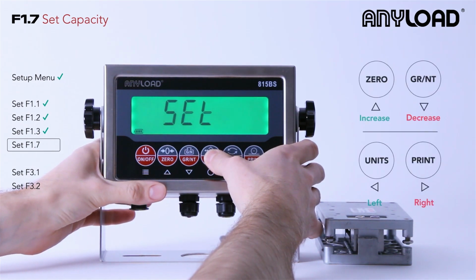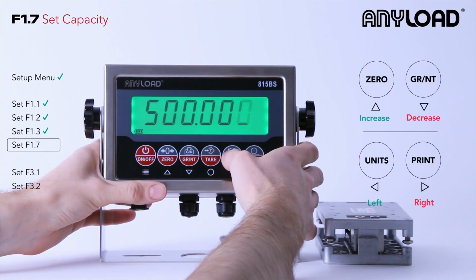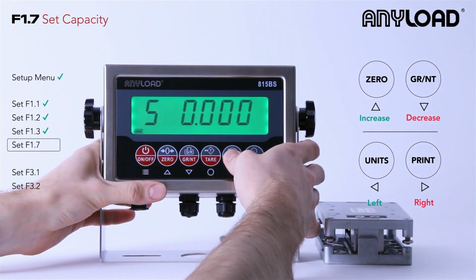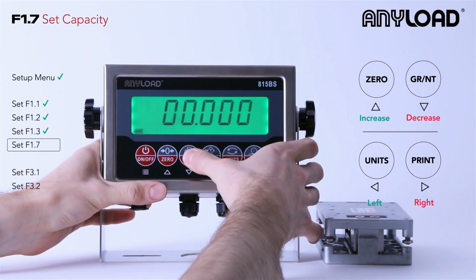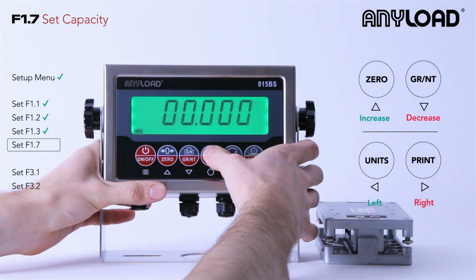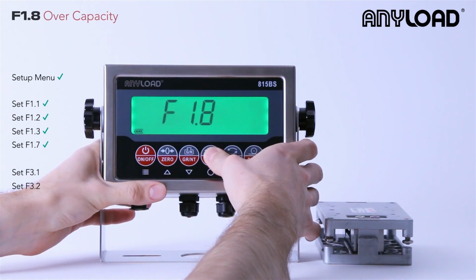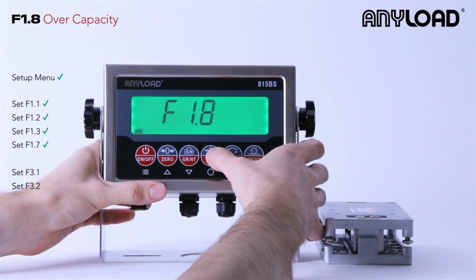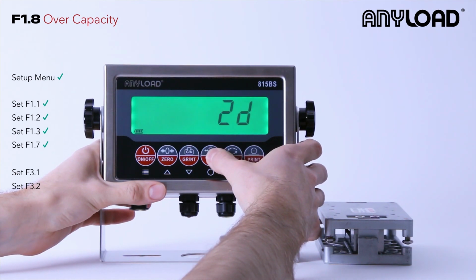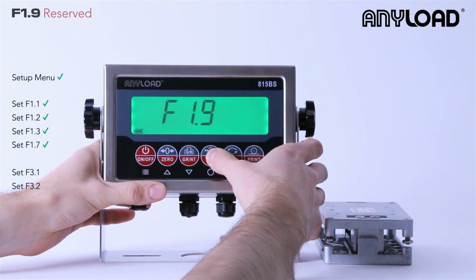F1.7, we're going to set our max capacity. So we wanted to set ours to 100 kg. So I'm going to move left using units, and I'm going to navigate up and down using 0 and gross. Press tare to confirm. F1.8 is our overcapacity. We're just going to leave this at 2 divisions. F1.9 is reserve channel, so don't worry about this one.